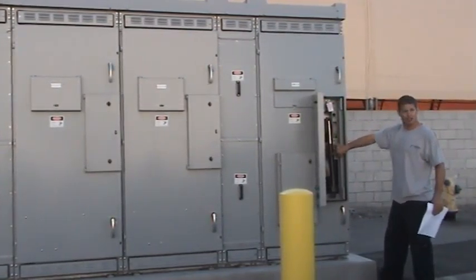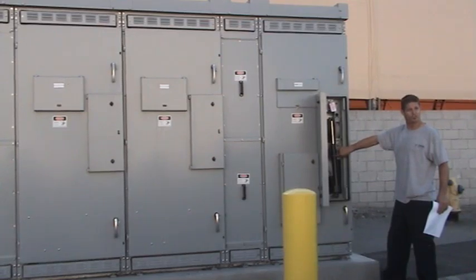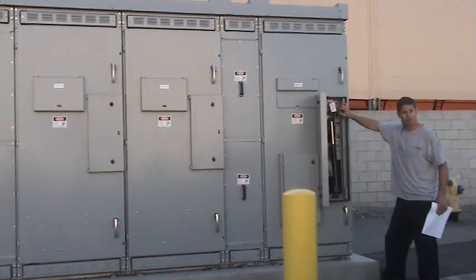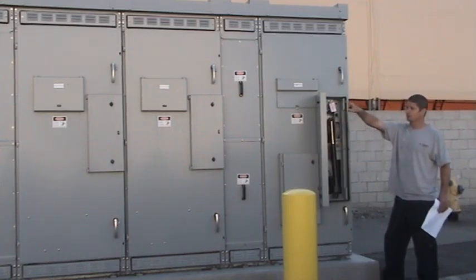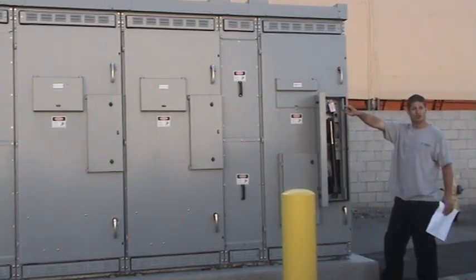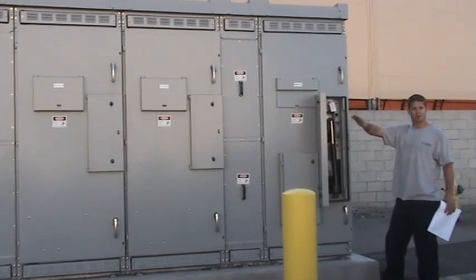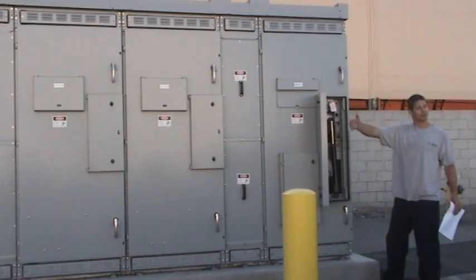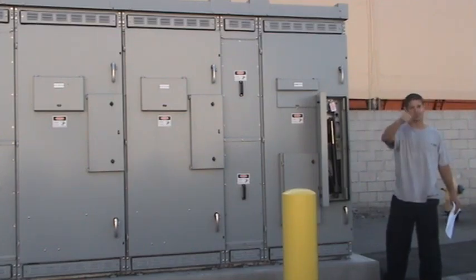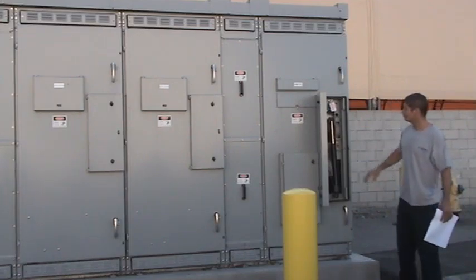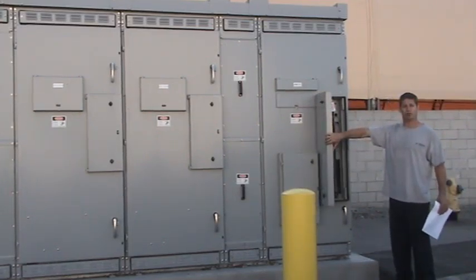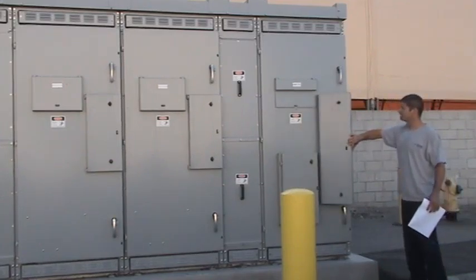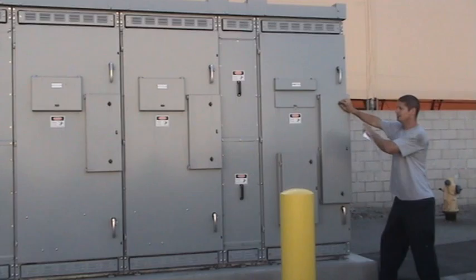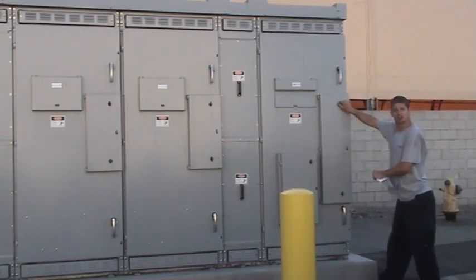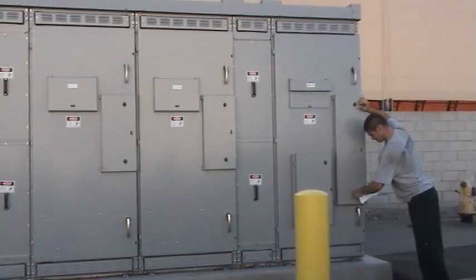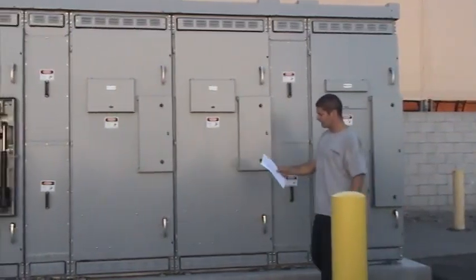They're powered actuators that actually close and open your switches. And you just flip open and close on the top here. Does it run from battery power? It runs from 48 volt battery power, so it should never be interrupted. The battery over here is on trickle charge, so either the generator's going or power's on feeding it, so you'll never have interruption. 48 volts DC power, and that is for the automatic switches, which would be a main and a tie here, and a main and a tie over there. So that is the manual operation.